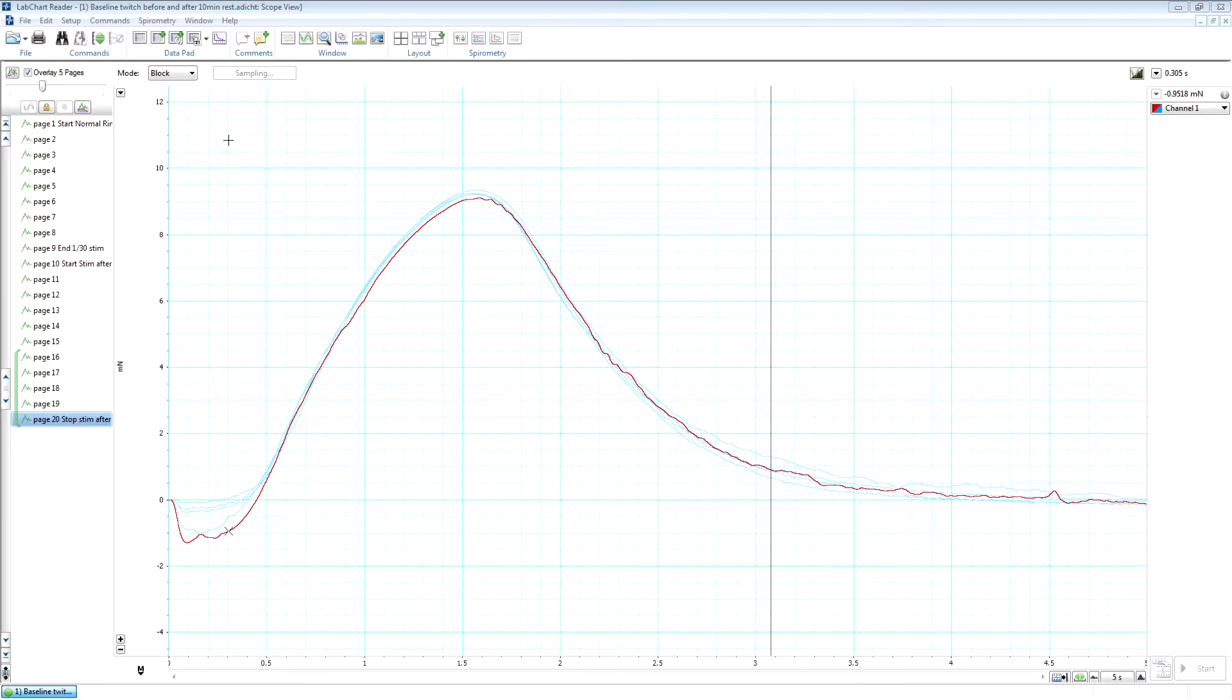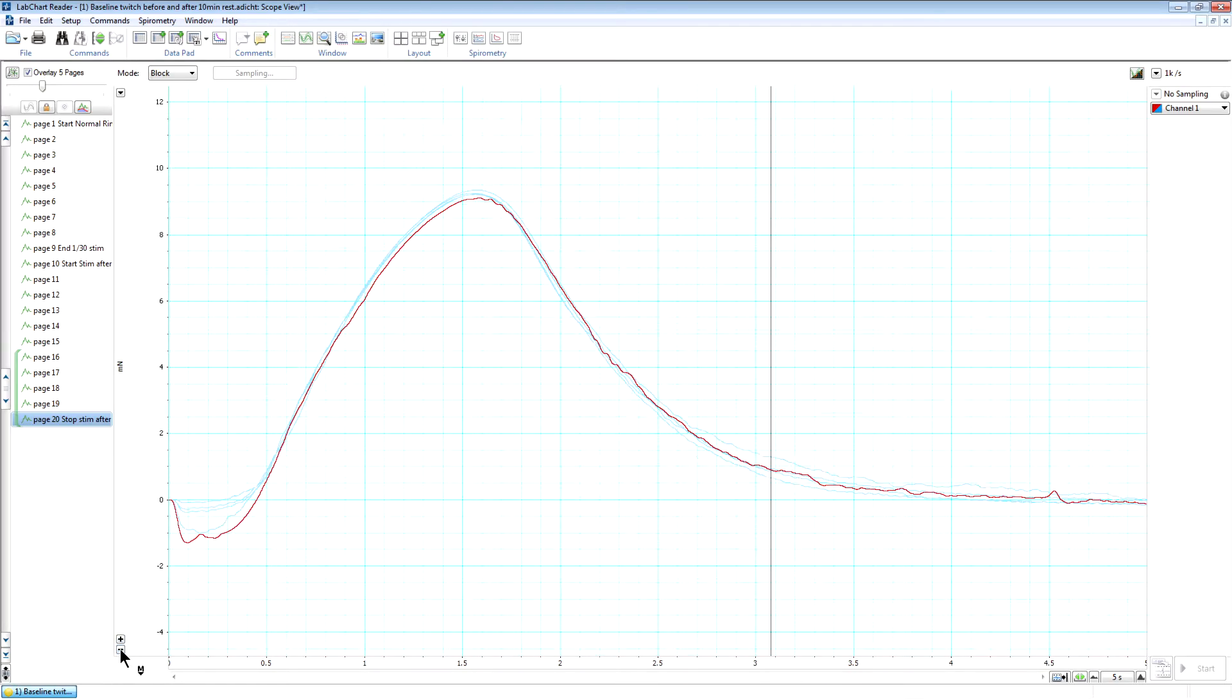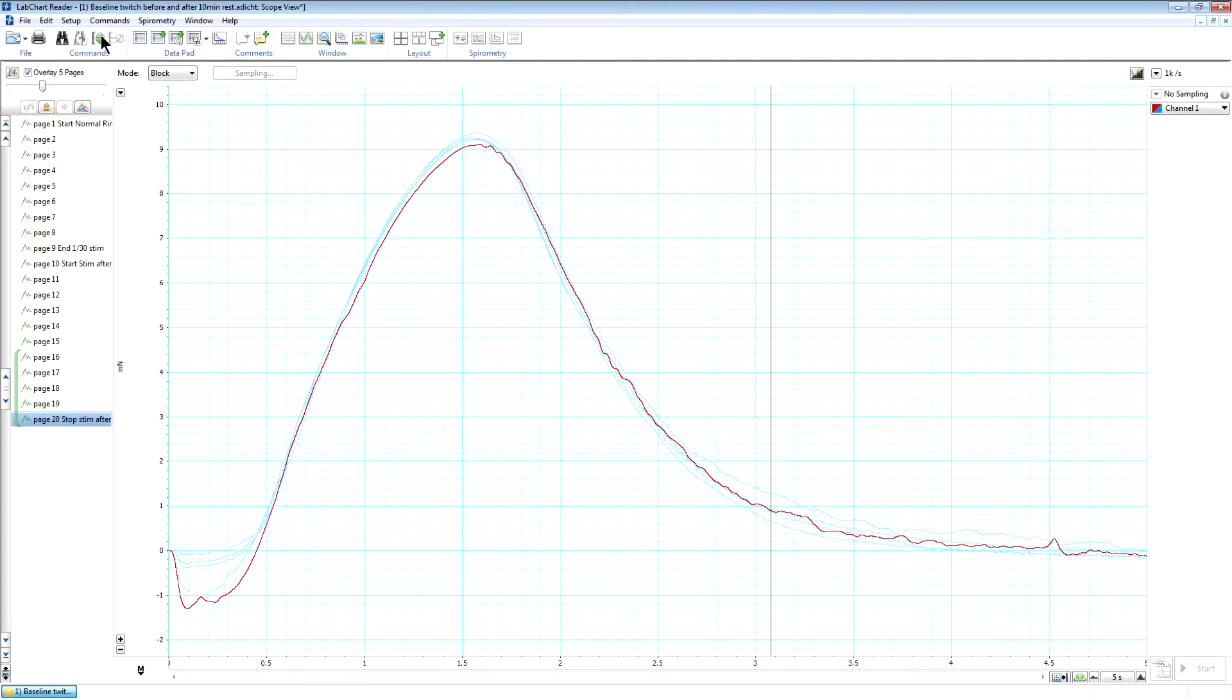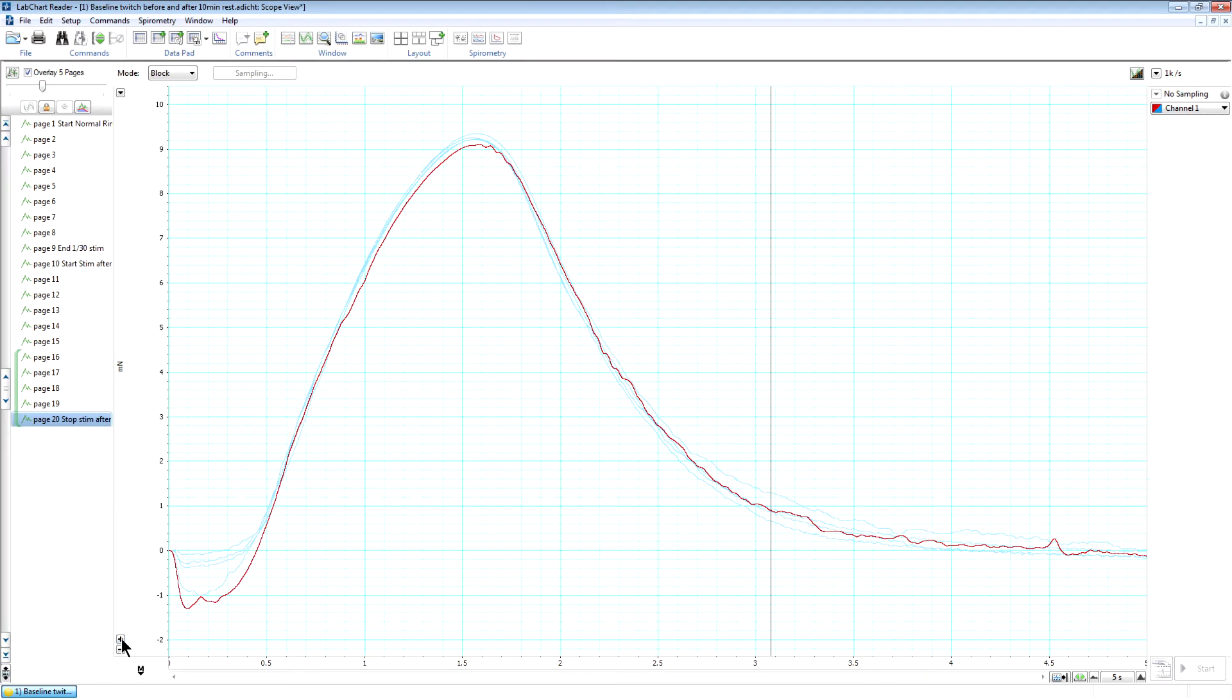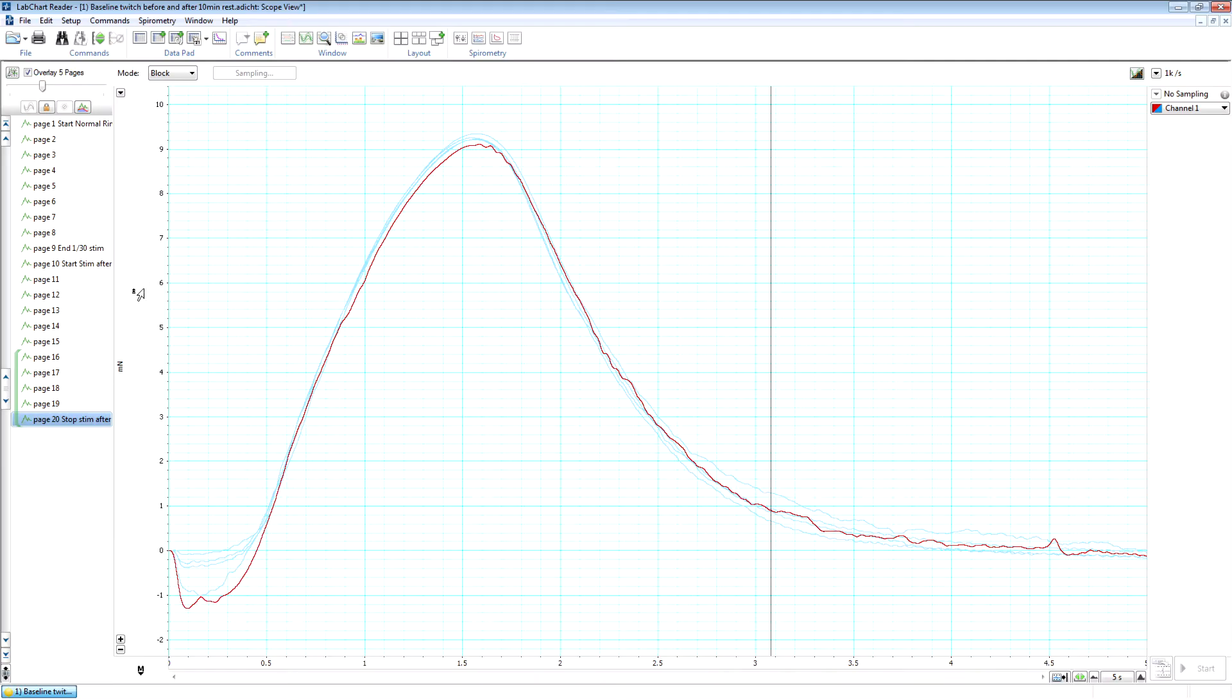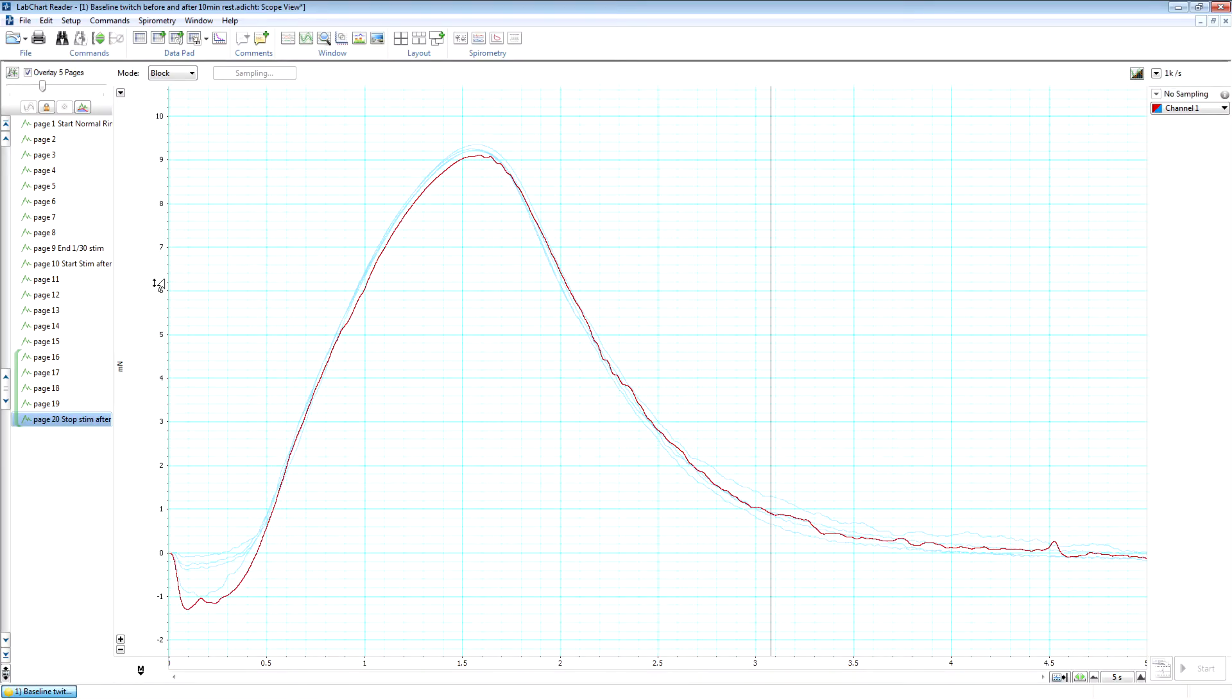So first of all, you can increase or decrease the size of the traces by clicking on the controls down here in the bottom, or by clicking on the auto scale button up at the top here. You can also move the trace by moving your cursor to the Y axis, and then when the cursor changes to a half arrow, you can stretch the trace up and down in the vertical axis.